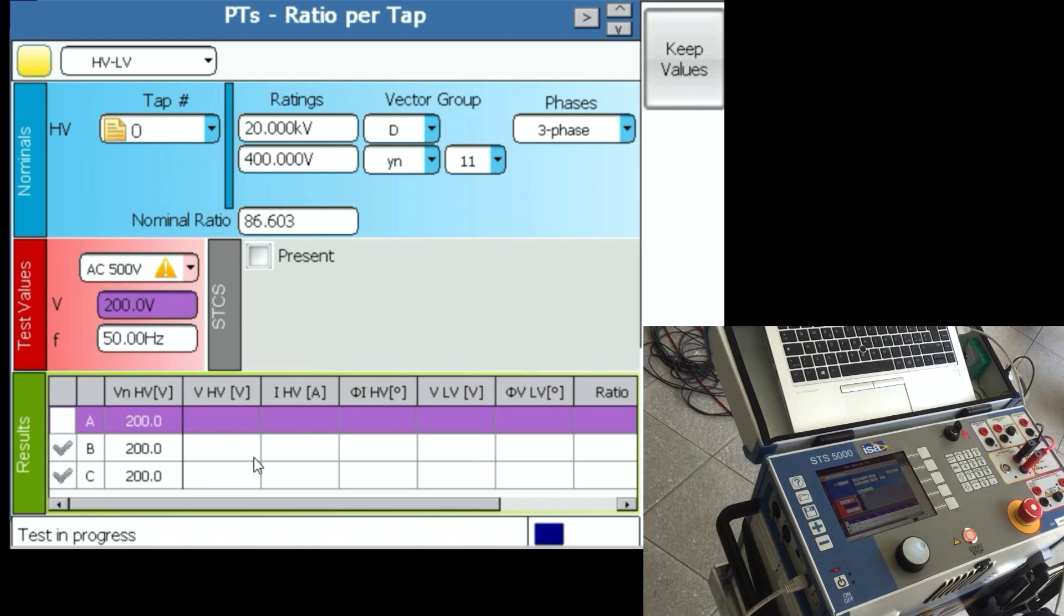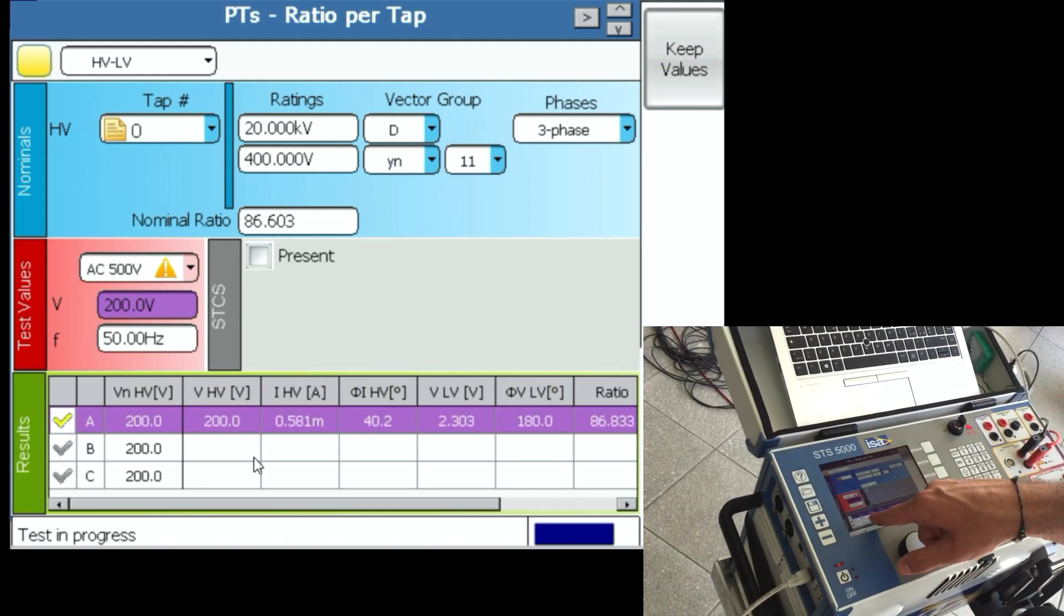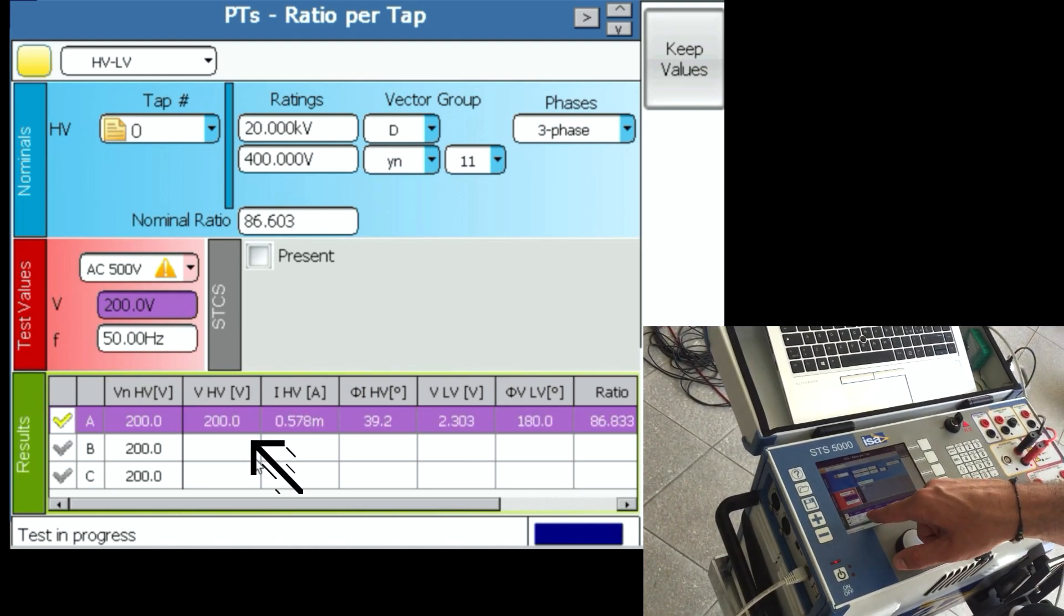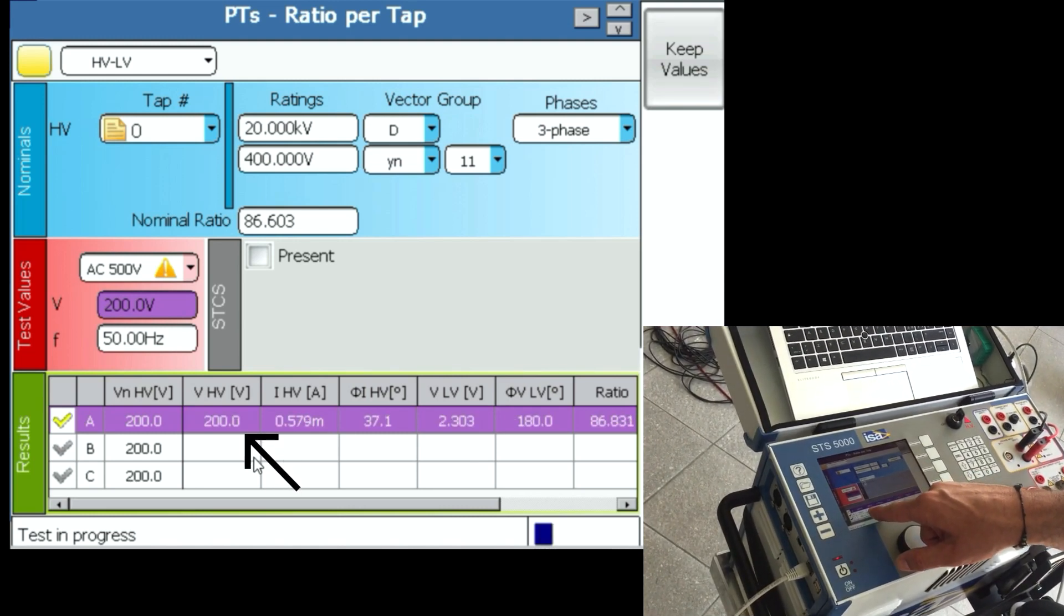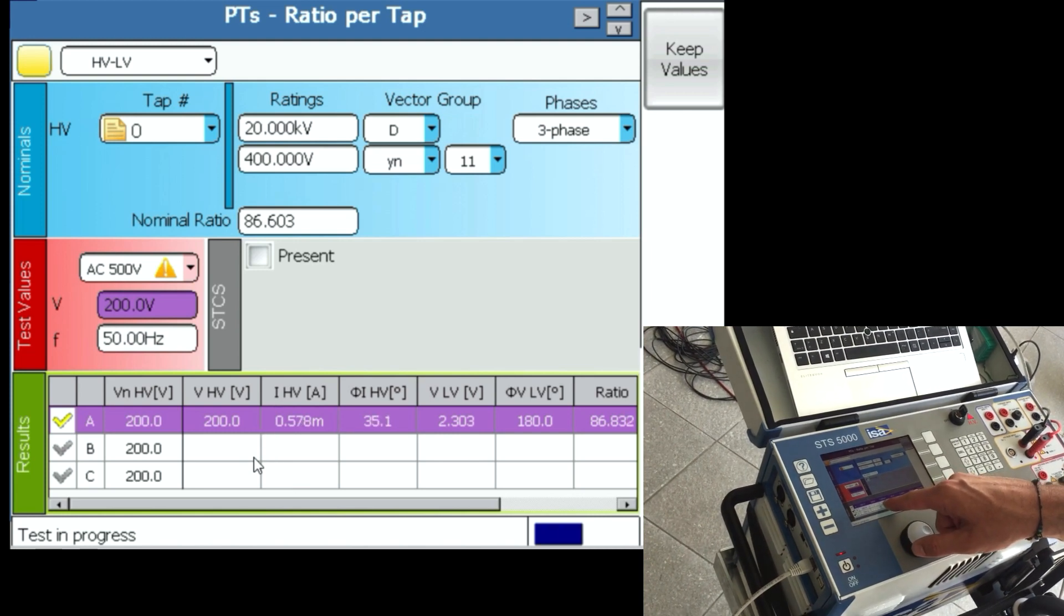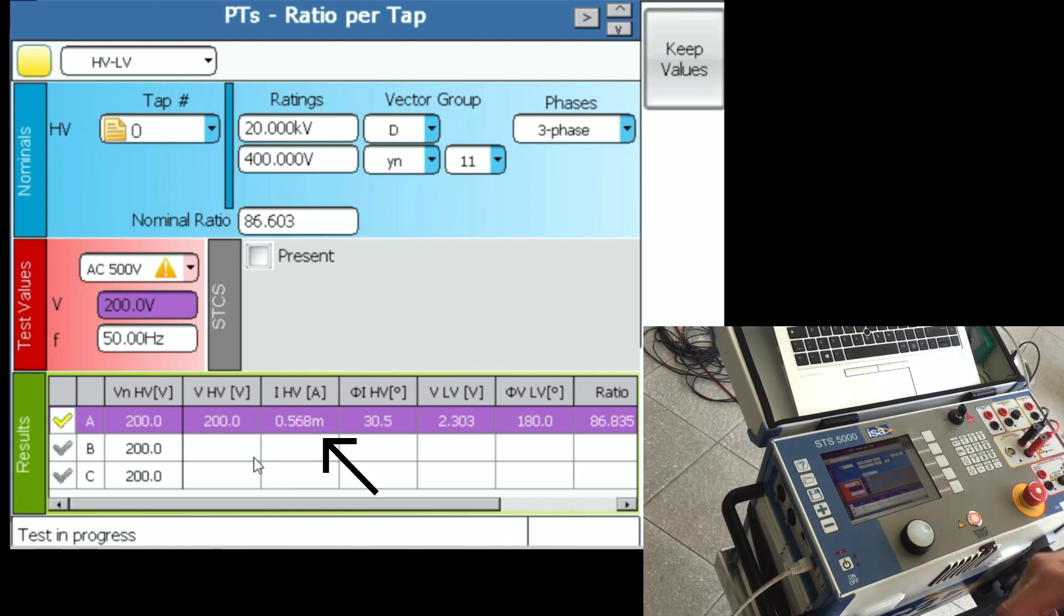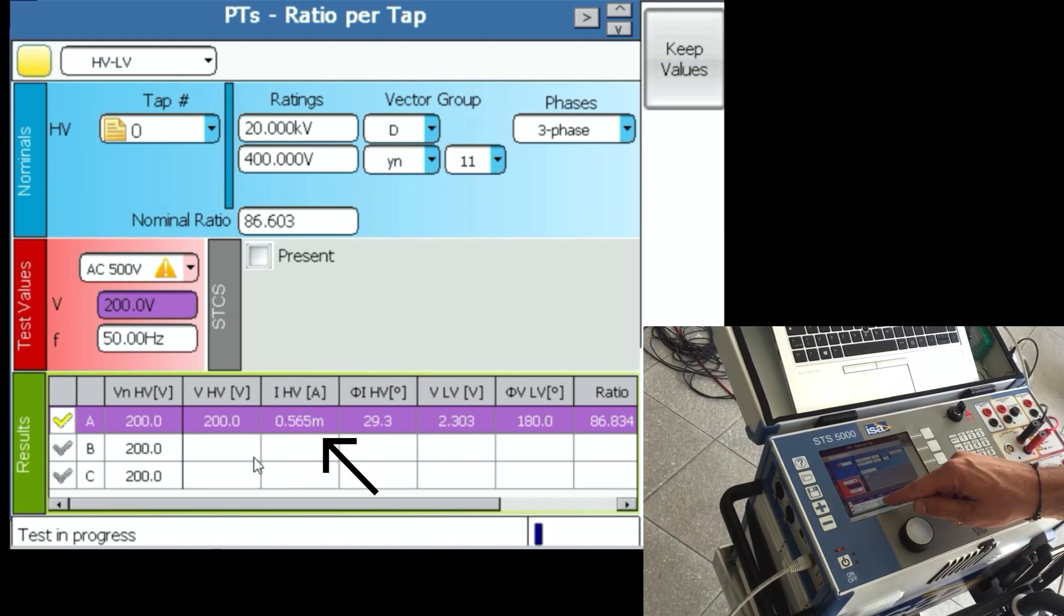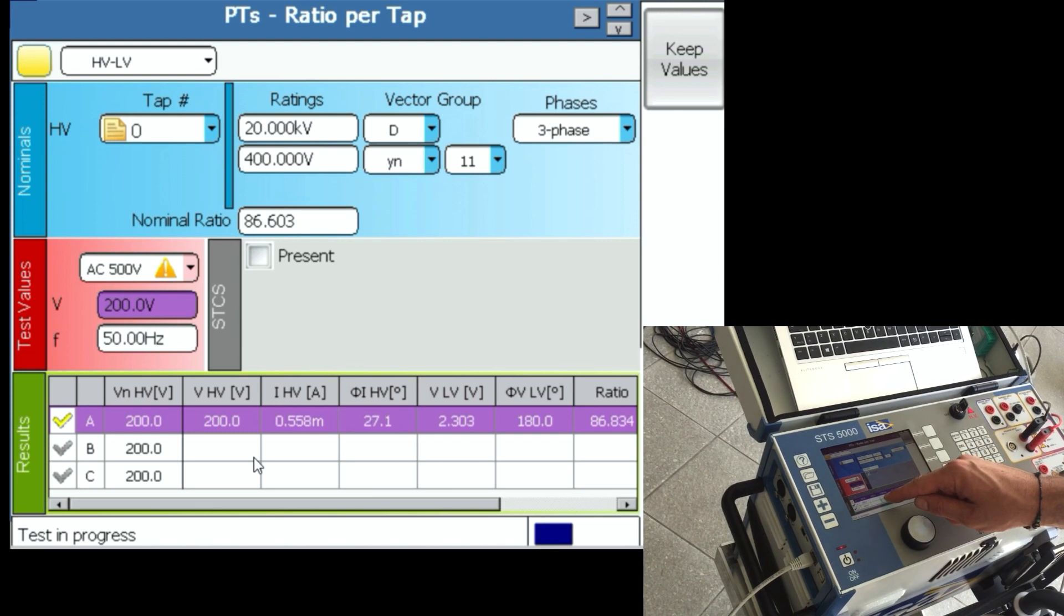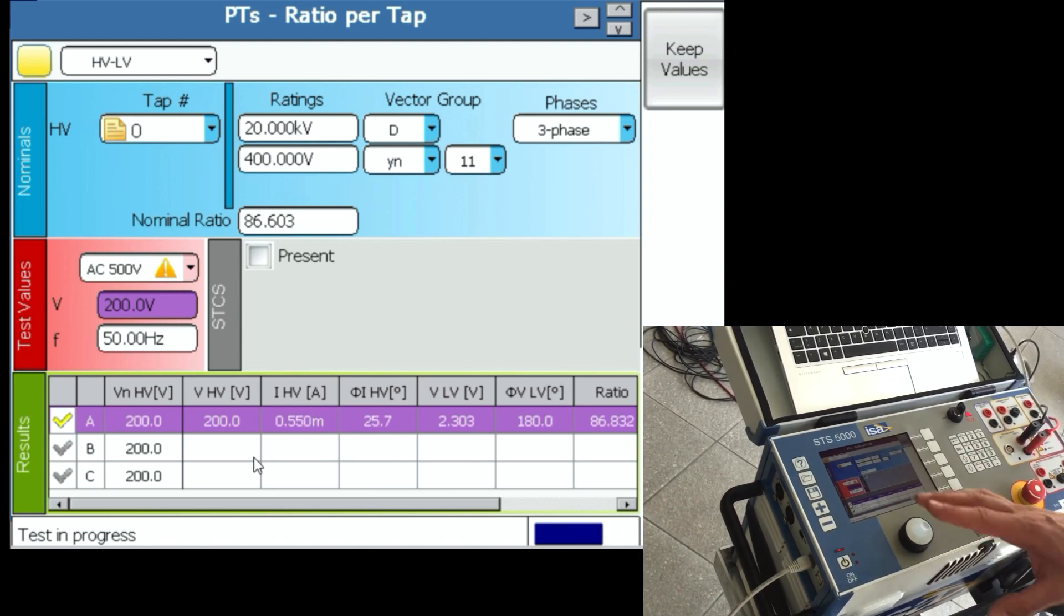What you can see right now is that we're generating 200 volts on the primary side and the current going into the primary side is 0.57 milliamps. Effectively this is the result, this is a no-load test result, but we'll talk about that later.